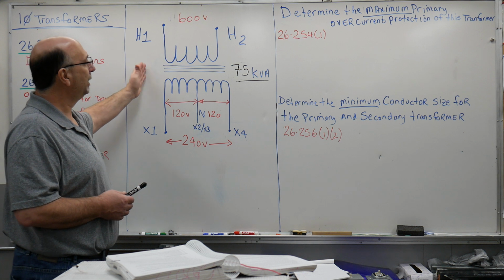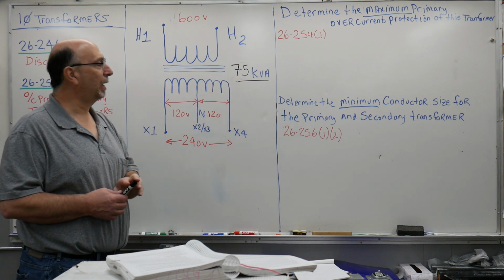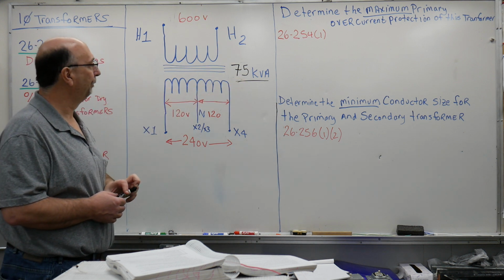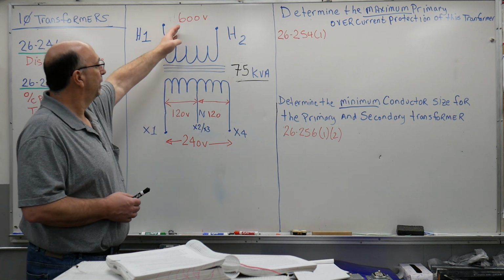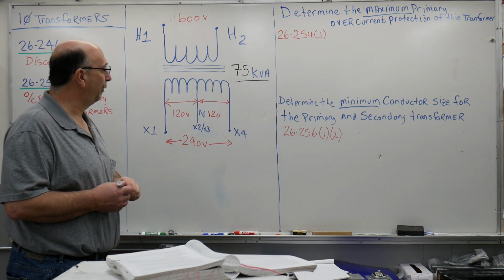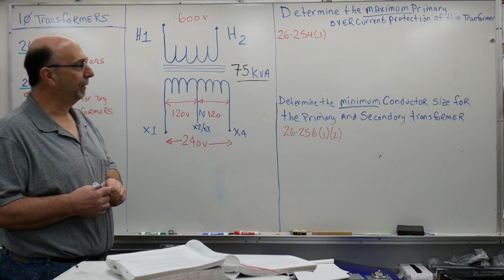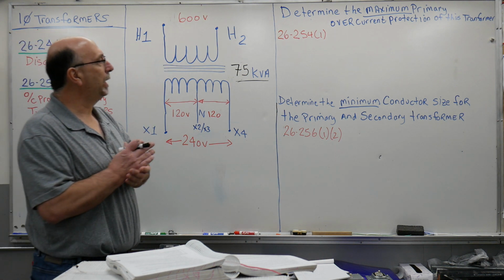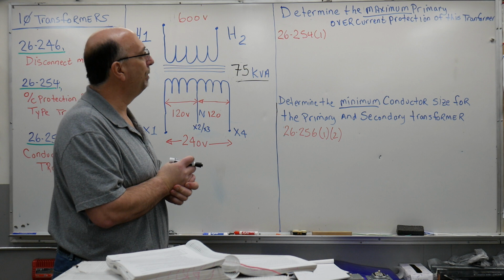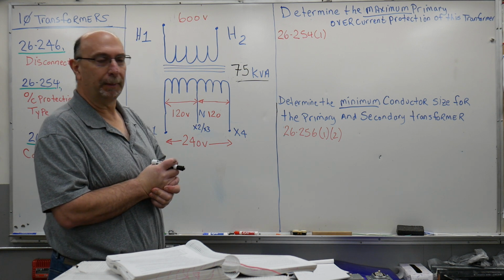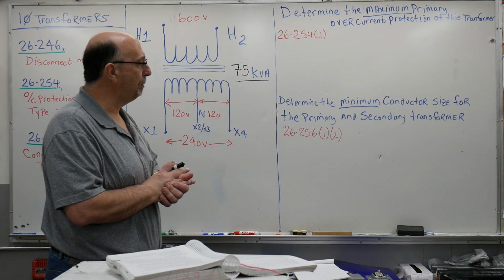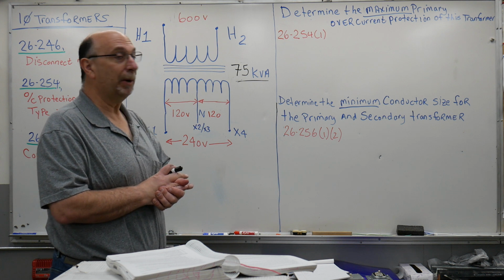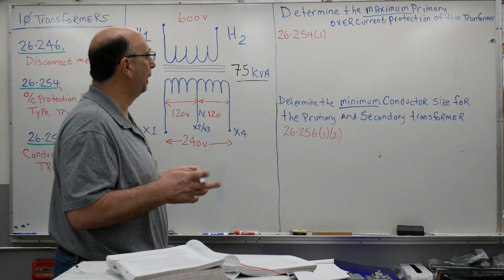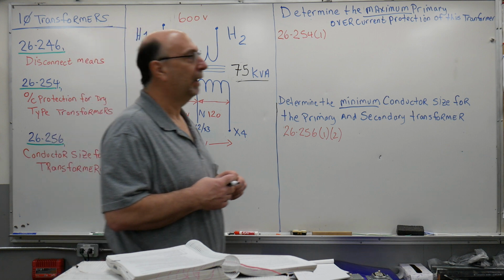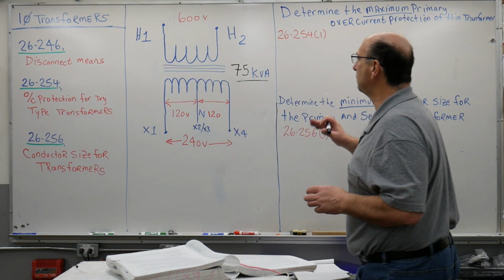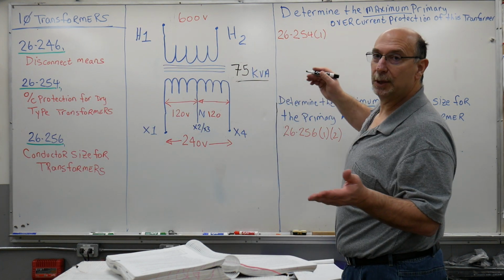We are next going to be using the Notorious 75 kVA transformer. Single phase, 600 down to 120, 240 volt secondary. Once again, we're going to determine the maximum primary overcurrent protection of this transformer. We're going to determine the minimum conductor size for the primary and secondary of this transformer. So by now, I'm sure you guys could do this in your sleep, but let's work with it.